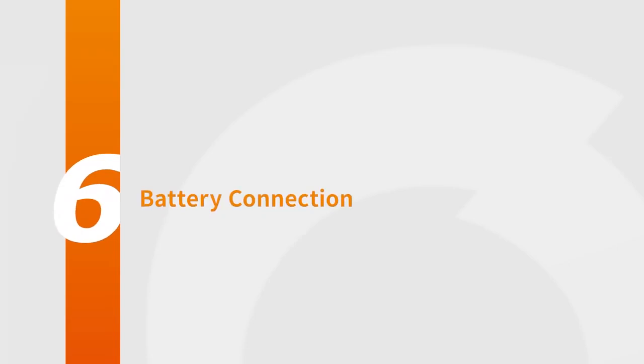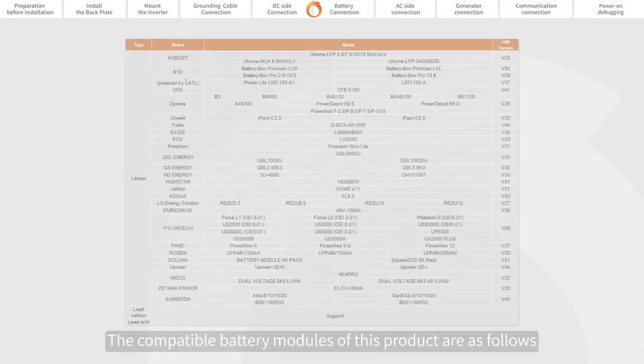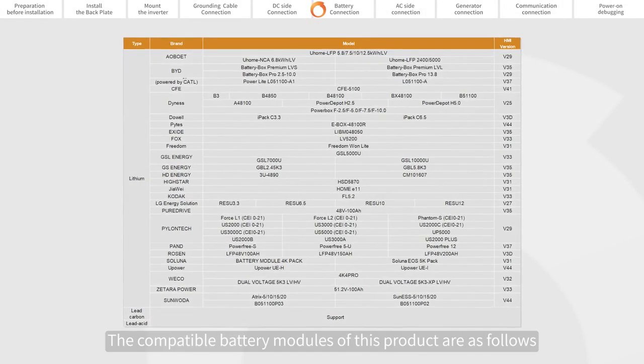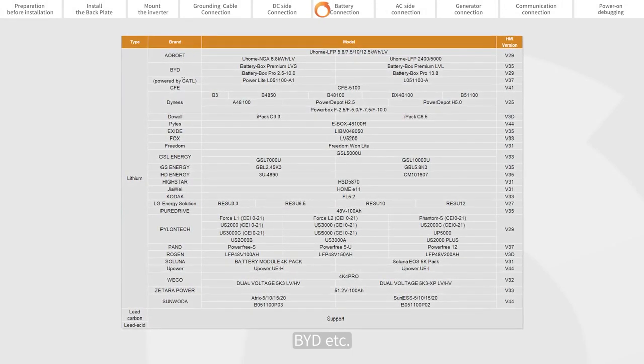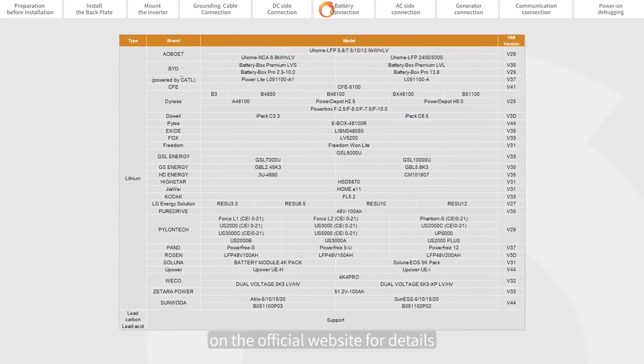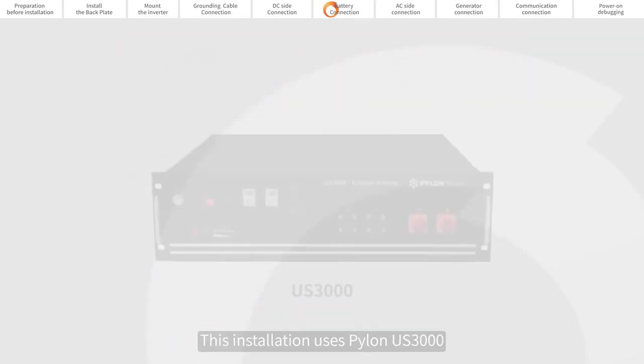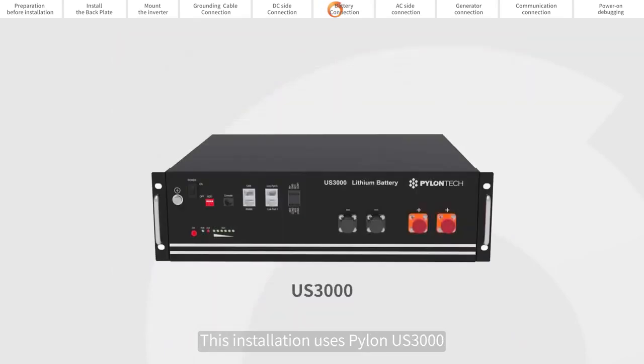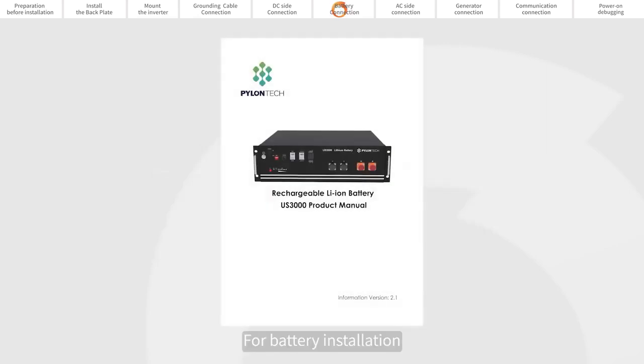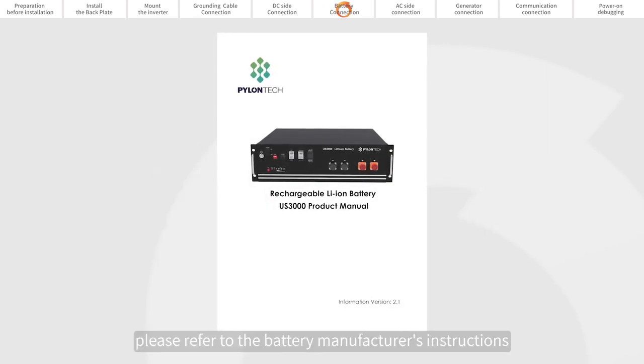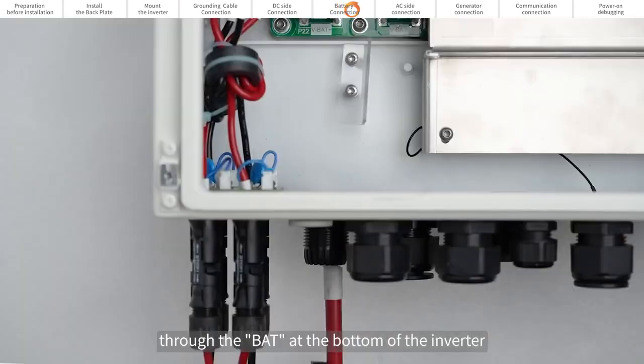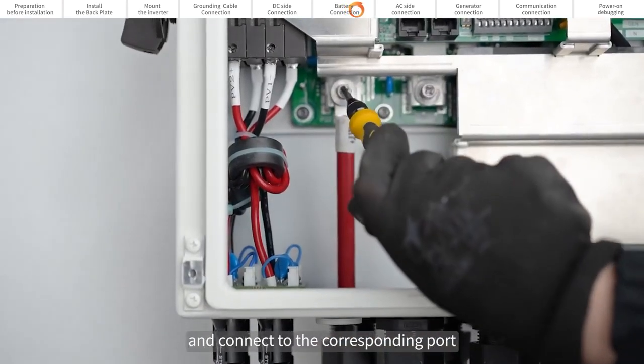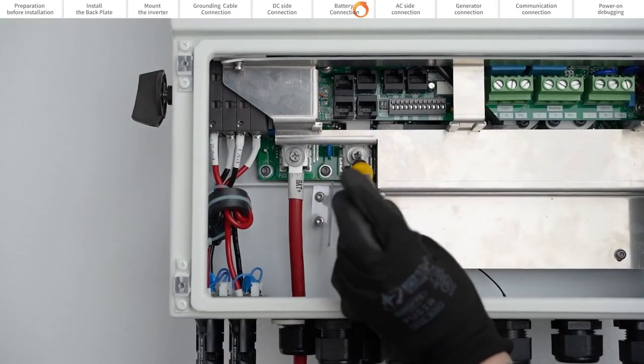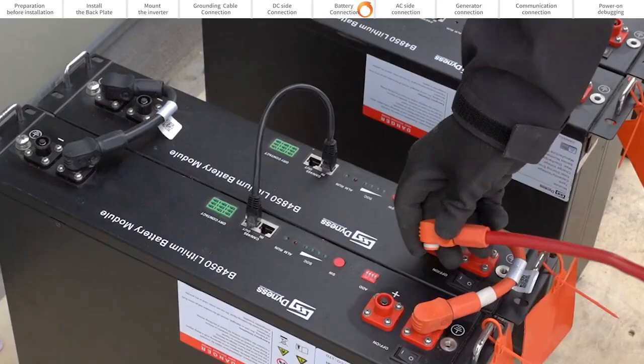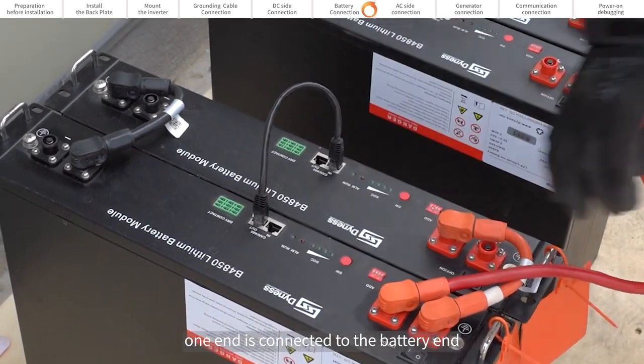Battery connection. The compatible battery modules of this product are as follows: Pylontech, BYD, etc. Please refer to the battery matching list on the official website for details. This installation uses the Pylontech US3000. For battery installation, please refer to the battery manufacturer's instructions. Pass one end of the battery power cable through the BAT port at the bottom of the inverter and connect to the corresponding port. The other end is connected to the battery end.